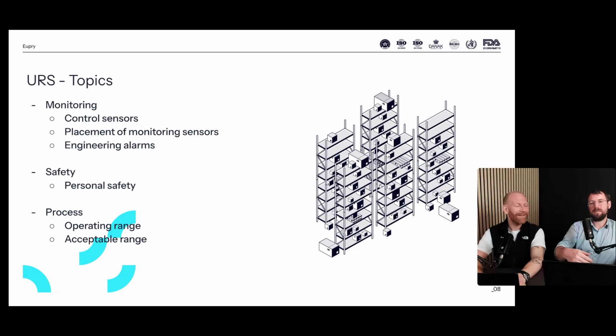So the next part is on engineering alarms, and that's also one of the places that we see a lot of times people will have put in the URS that you need engineering alarms on failures. That's fine. You should have engineering alarms on when the system is operating at over capacity, or whether there are doors that are not being closed. But actually, one of the things that we see performing really, really well is that you have engineering tendencies or engineering reports as part of your expectations for a system.